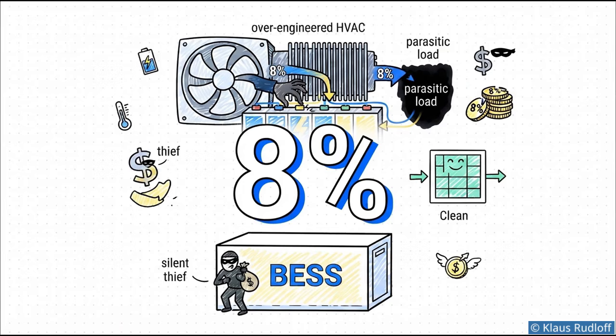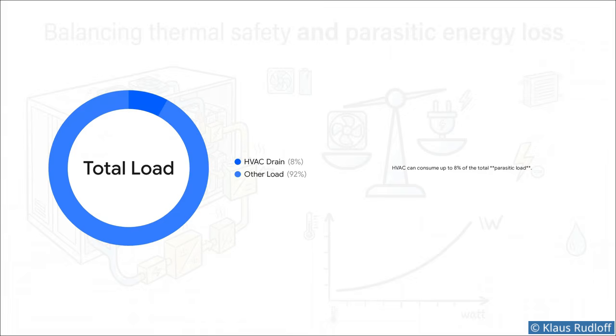The crucial point here is 8%. It might sound like a minor annoyance, but in the world of utility-scale energy it's a staggering number. An over-engineered HVAC system in a BESS container can consume up to 8% of the asset's total parasitic load — every sliver of that 8% represents power that was generated and stored in the battery, but then completely wasted on redundant cooling instead of being dispatched to the grid.